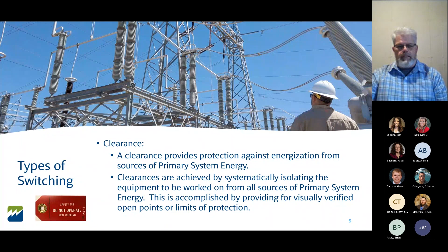The other thing we have out there is a hotline order. Notice I didn't say the word protection—with a hotline order, you have no protection. The crew works on or near the line while it's energized. Sometimes the system requires us to work on equipment that is energized, and to do that a little safer, we place a hotline order on the line. We go in and turn off the automatic reclosing 79 relays, and the crew will work on or near the line. The HLO supervisor makes sure the crew maintains minimum approach distance, because if they violate it and get too close to the energized conductor, they may flash it over. If that happened, we do not want an automatic test or re-energization of the line, because we'd hurt you once and then we'd hurt you twice.